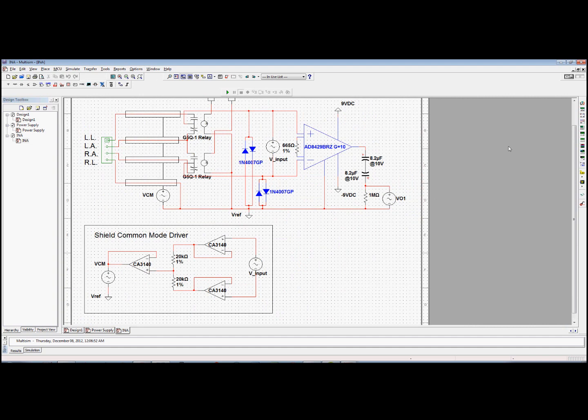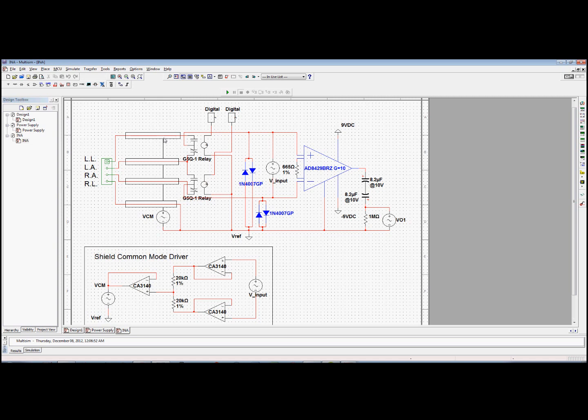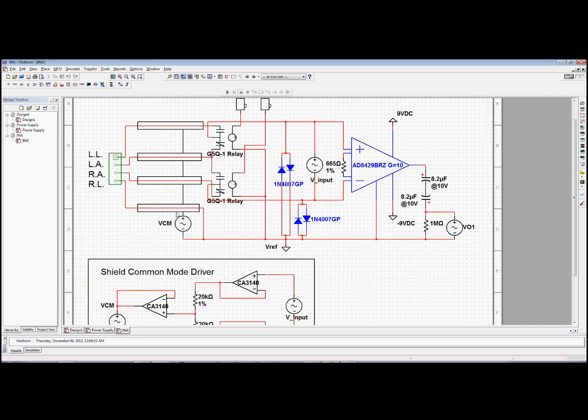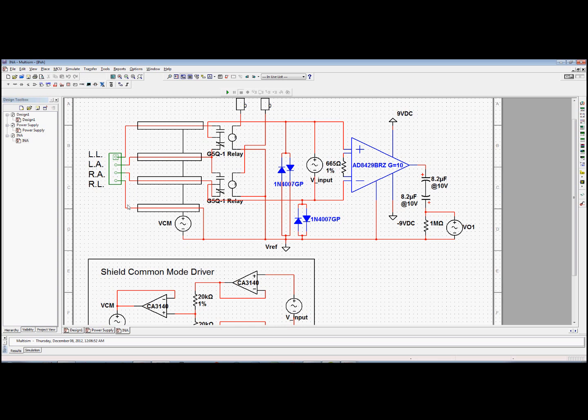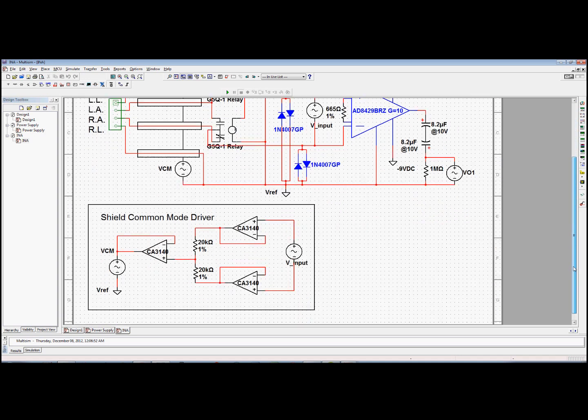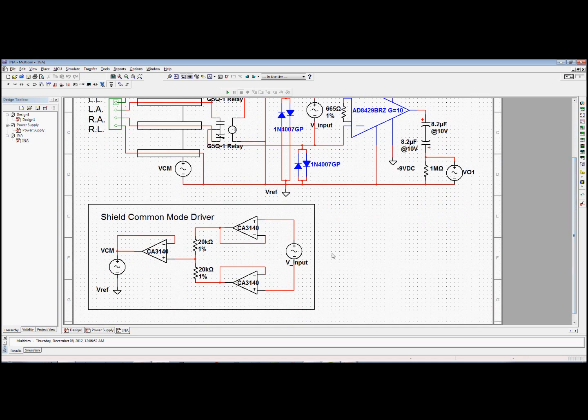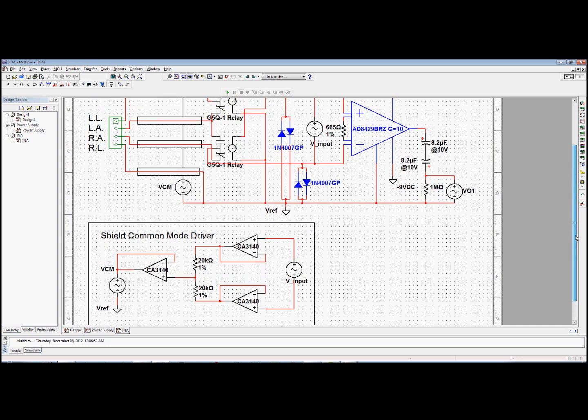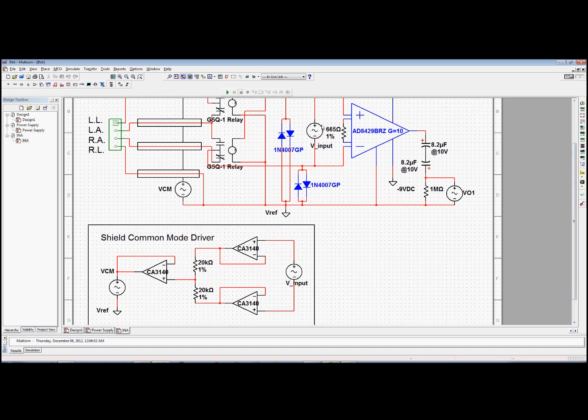Now let's move on to the shielding part of the cable for the leads. You want to shield it in a way that you have the common mode signal being connected to the shield. So that your signal line, your ECG signal line, when looking out to the world, it will see itself. The common mode, there will be no capacitive coupling here. Minimal capacitive coupling between the wire and the rest of the circuit. So in a way, it's good to have a shield common mode driver that creates that common mode signal. This will be done by using the input right here, the differential input.